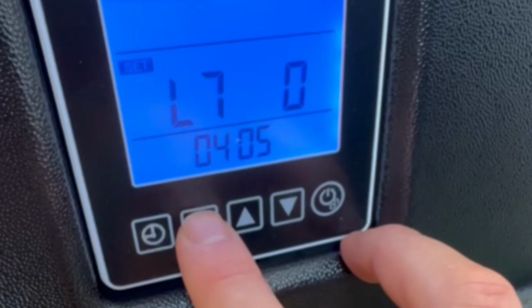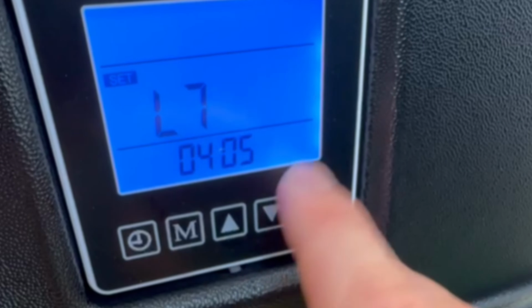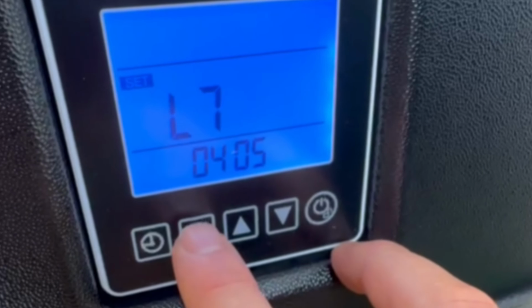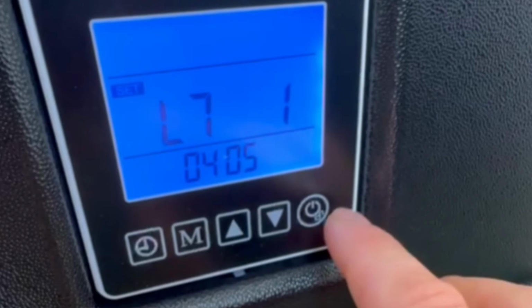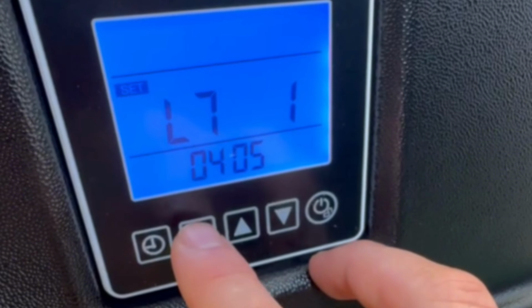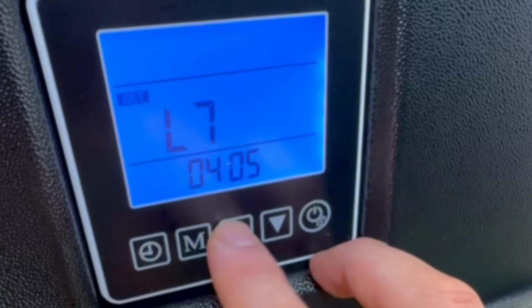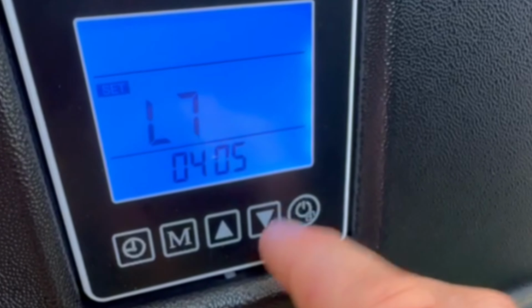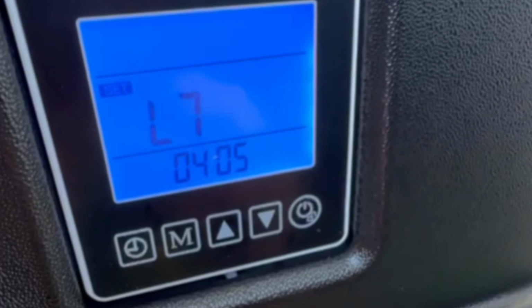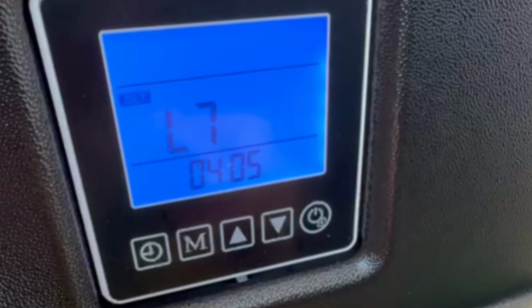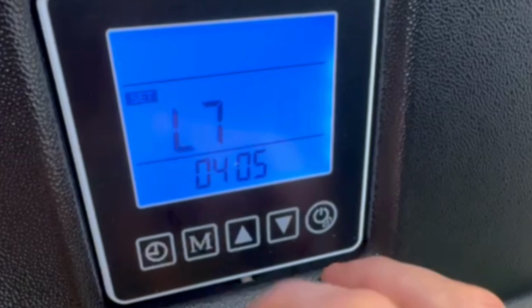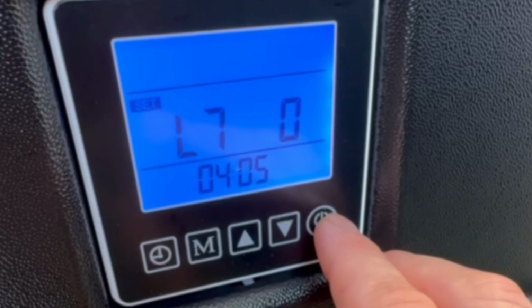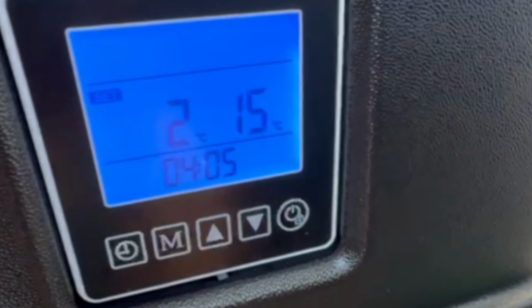if you change that to a 1, you would press the M, and then you change that to a 1, you press the M again to close the setting, and then you just press that to go back to the main menu. But we actually want it at 0. If you were to change it to 1, then it would mean that the pump or UV would go off when the fan goes off on the chiller. So let's confirm that 0 is what we want. Simple as that.